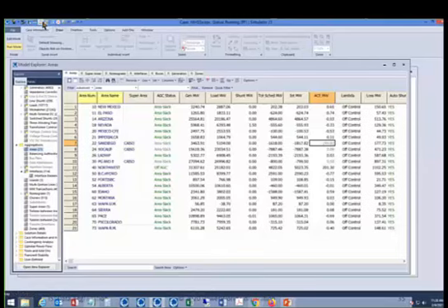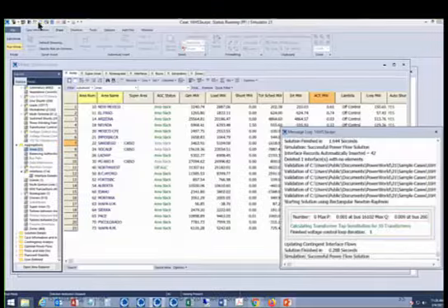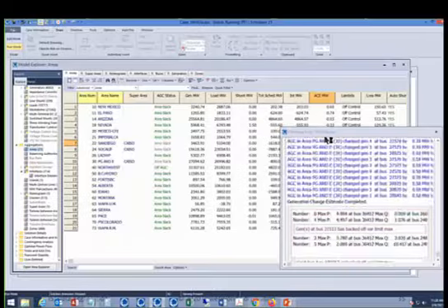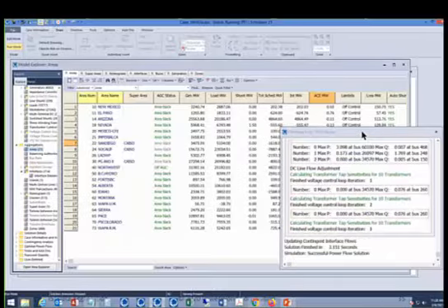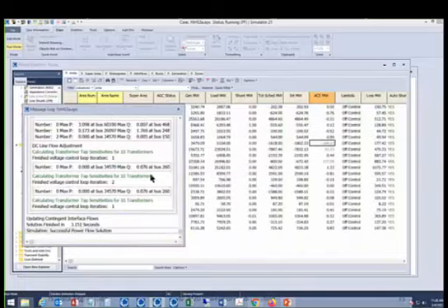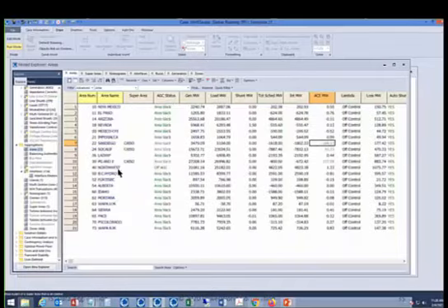So what I mean by that is I'll turn my message log on up here and solve the power flow case to make sure we're good. And now my area Northwest ACE is now 1.33, which is within the tolerance, so that's good. But these others are kind of like all over the place, but they basically sum to 0. So again, it's not enforcing the individual exports of each member, but rather it's using the super area to act as one area, even though the other areas still exist. They're just not on control.